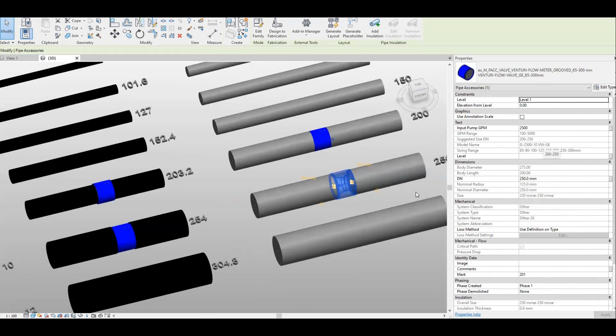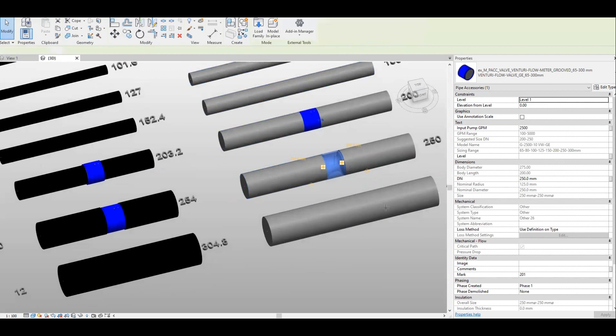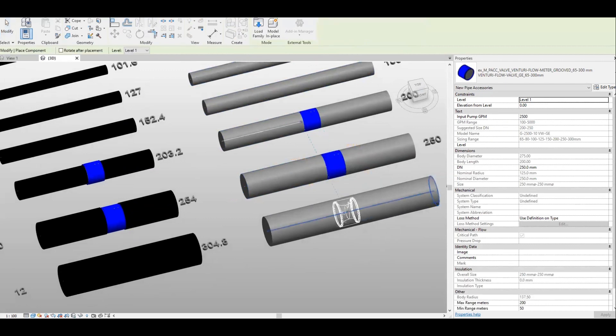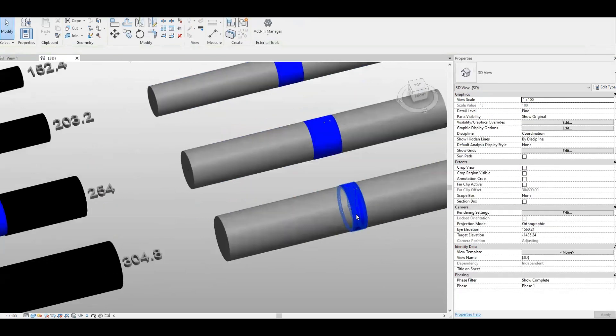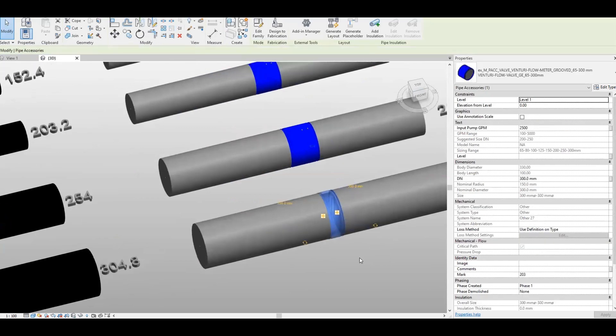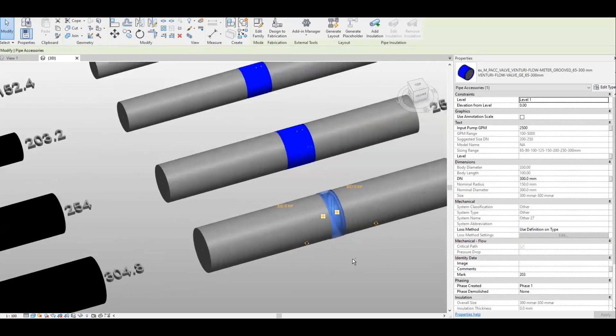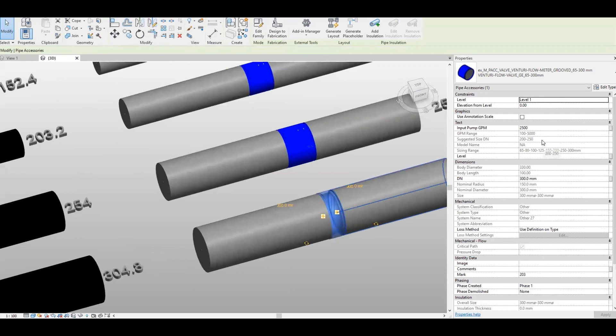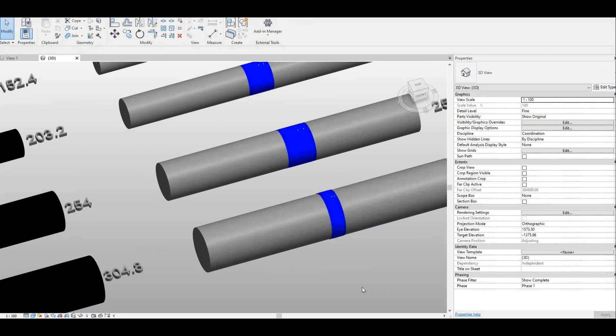At 250 it's still correct based on the input pump capacity. But if I go to 300, I think 300 is out of range already. You can see it looks a little odd because it's much smaller, meaning it is already wrong. The sizing range for this flow meter valve is 200 millimeter up to 250 only. If you place it to 300, you know this one is wrong and you need to search for another type of flow meter with a higher range.